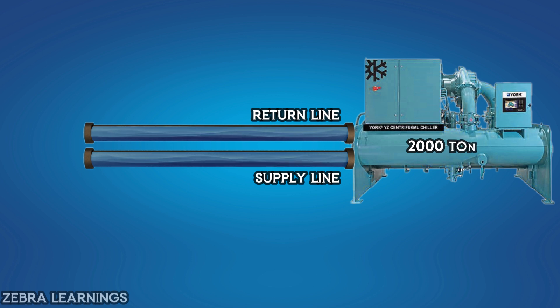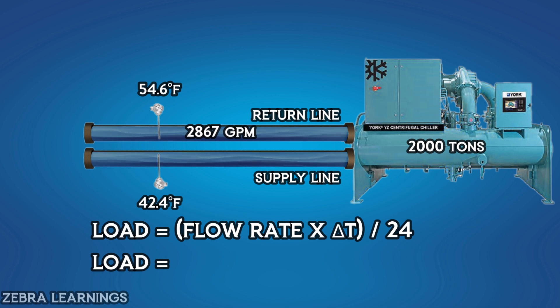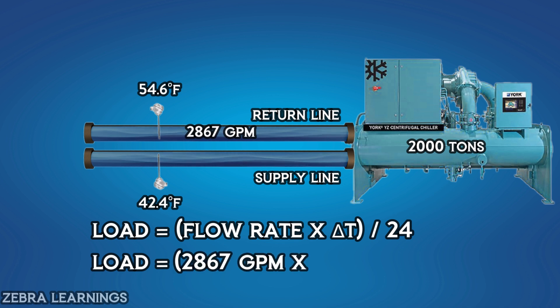A 2,000-ton chiller has a chilled water flow rate of 2,867 gallons per minute, with a supply water temperature of 42.4°F and a return water temperature of 54.6°F. Now let's apply these values in the formula.